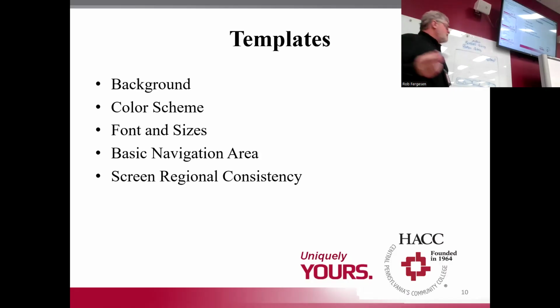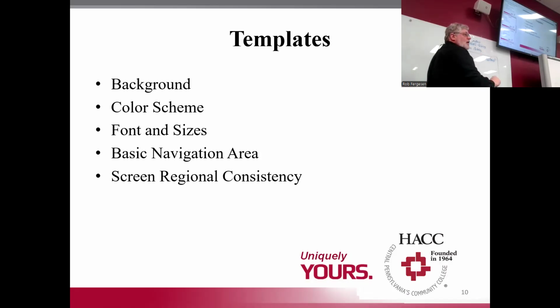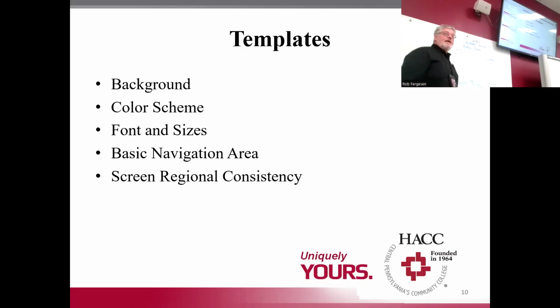Today, 30 years later, we're all trained to see navigation on the top bar as some sort of Microsoft-looking file tab. So we're trained to put navigation on the top. I liked it on the bottom because I wanted people to look at the top of the screen for the most important information. Like the very top of the screen, I like to have alarm information or critical data for the machine operating. But now we're all trained to put the menus on the top, so we'll put the alarm and critical data somewhere else.